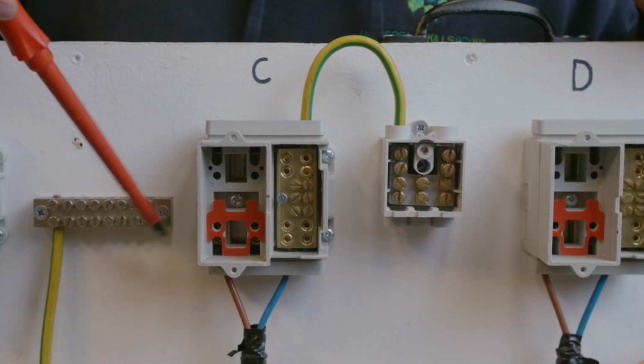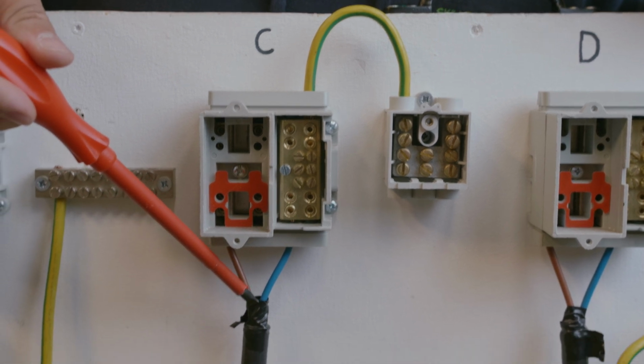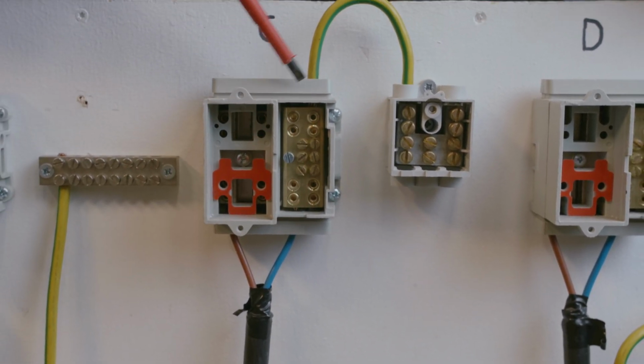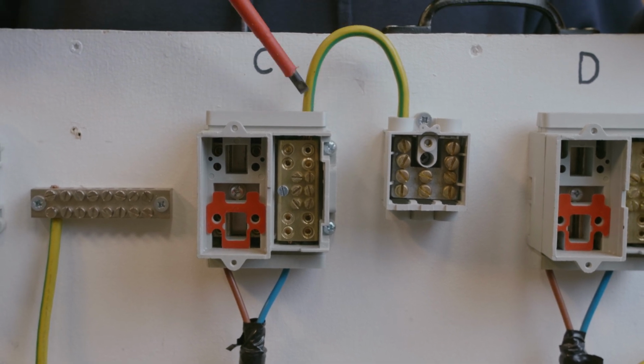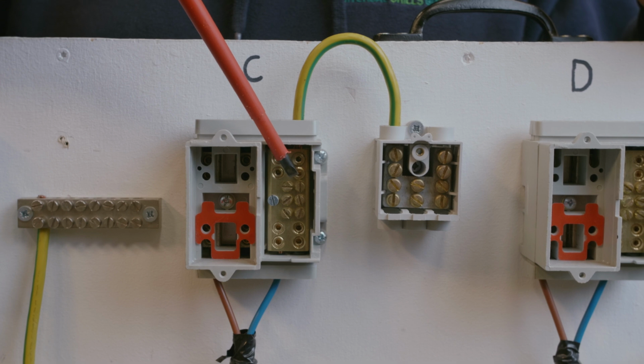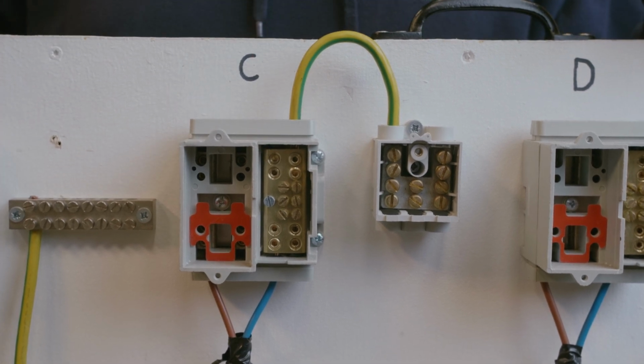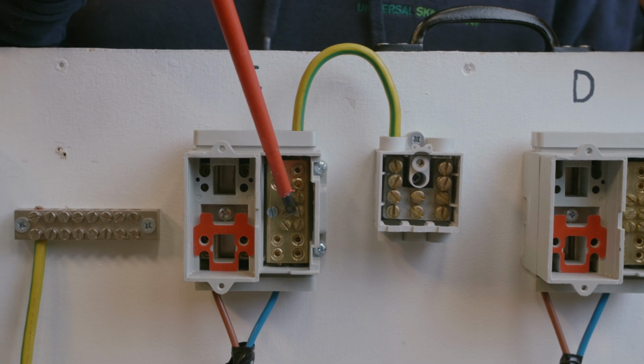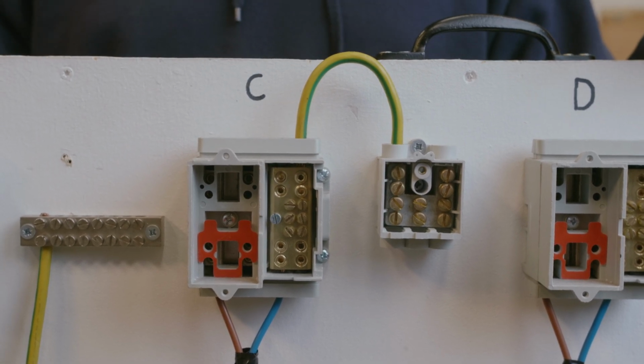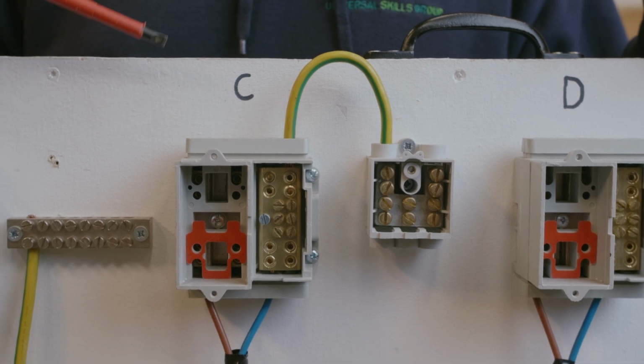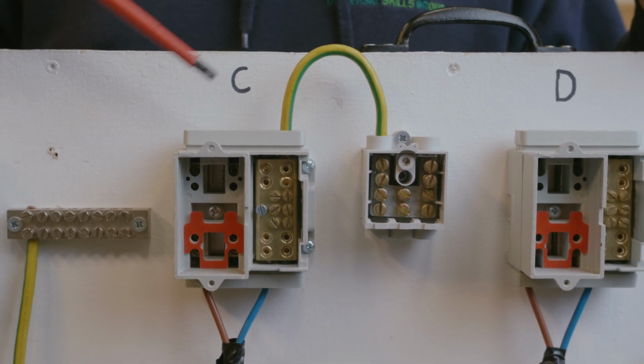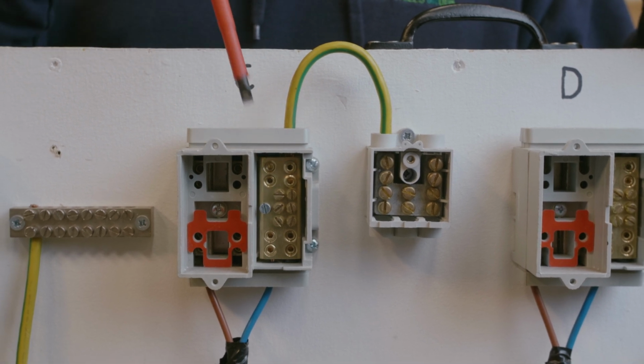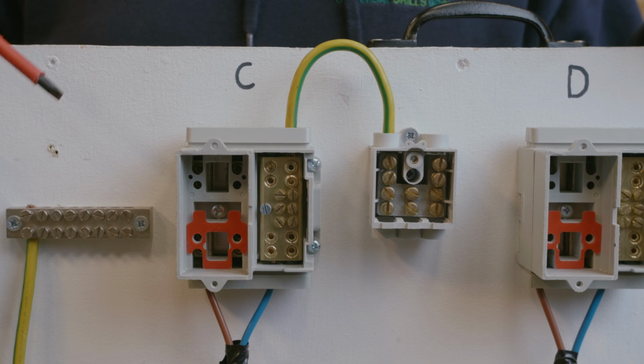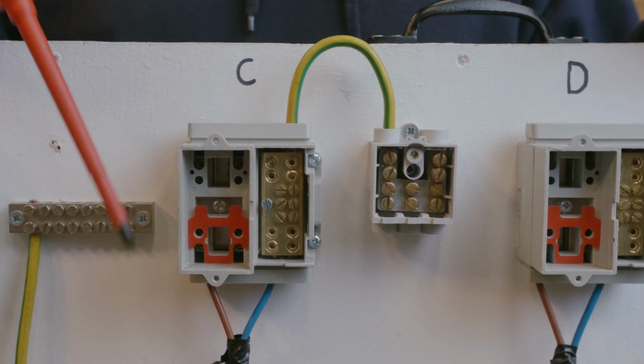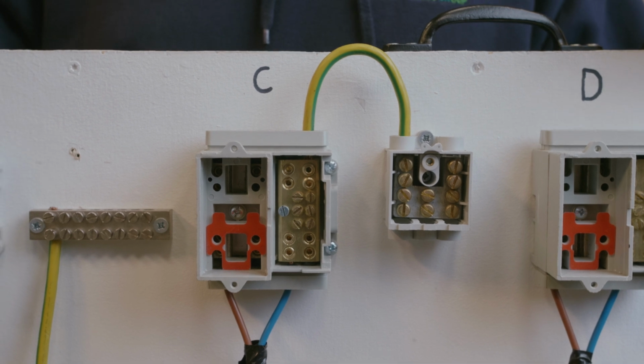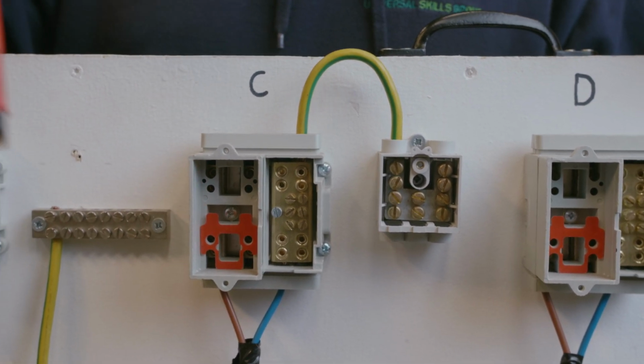So as we look closer into this setup, you can see that obviously you've just got the line conductor and the neutral conductor. But obviously on the top of the cutout, we've also got the earth attached, and which seems to go straight into the neutral block as well. Okay, the reason behind that is because the neutral and earth are combined, and that's where the C comes from in the TNCS. So C meaning combined. So what that means is the neutral and earth are combined all the way back through the supply, all the way back to the supply transformer, and along that neutral cable it is teed off, and it can go to earth spikes, earth mesh, that kind of stuff, and it's earthed at various points along the way.